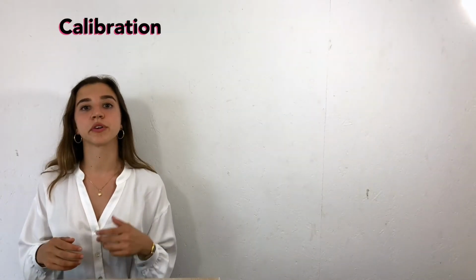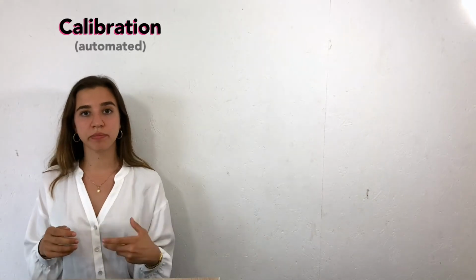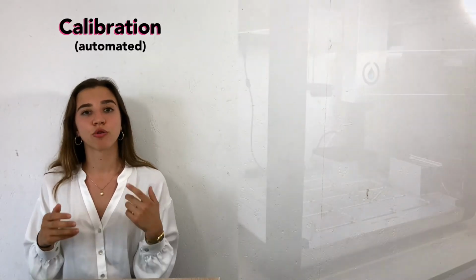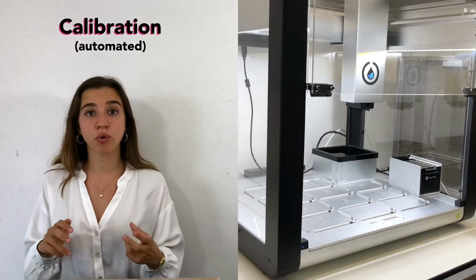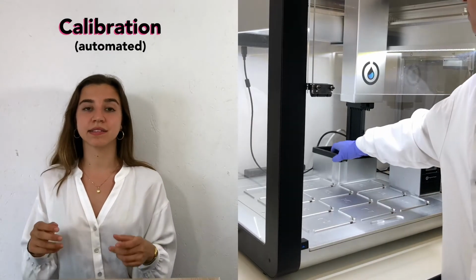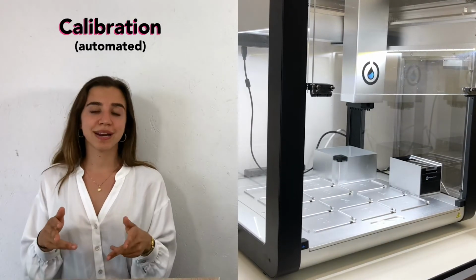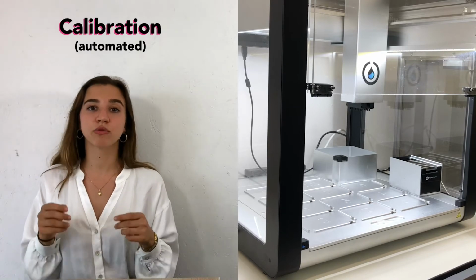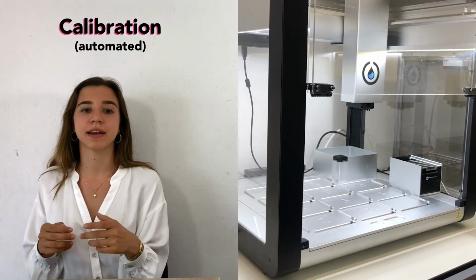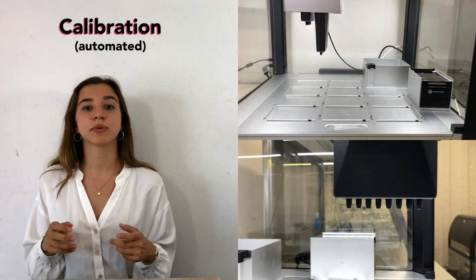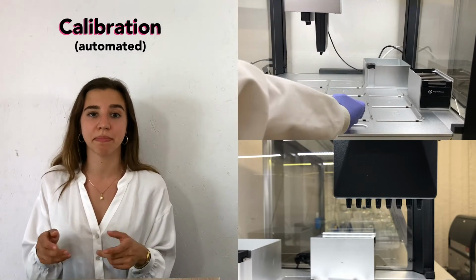The first stage of your OT-2 calibration is the automated calibration of the pipette. Remove all labware from the deck, and very importantly, remove the bin as this contains sensors underneath it. Do note that you can keep the magnetic module in the robot as long as it remains to the side. Now attach a spare tip to the backmost channel of the pipette.